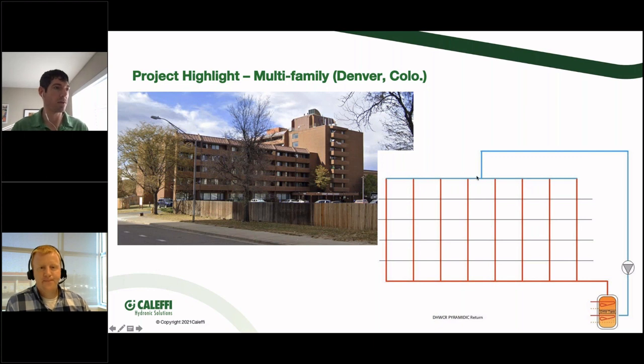And then the other thing we've heard before is that if this is properly balanced, you don't need any sort of thermal balancing valve. If it's balanced per the engineering recommendations, it's going to be fine. I think that works on paper, and it may work in reality, but this riser may have one tenant, and this riser may have a full house on. It's completely dynamic. So the ThermoSetter was a great pick for this because it's dynamically adjusting to the dynamic tenants in a really complicated, really confusing building that was not designed properly. It's not a reverse return, it's not the same length, it's not the same number of fixtures, and they're on and off at different times too.